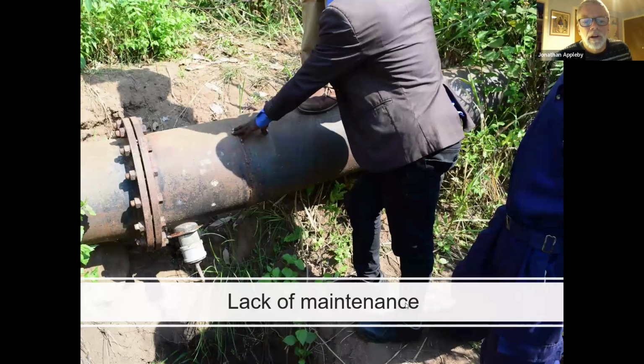One of the main issues over the years was lack of maintenance. Faults, when they occurred, were often left unrepaired or just bodged a little bit. Behind that is the fact that the hospital never had any money for that sort of thing. Money is very tight, and in these mission hospitals there's never enough funds for whatever they want to do. So if somebody comes along saying, 'I need a few thousand pounds to repair this,' it doesn't always get done. The cleaning of the dam hadn't happened very often, so silt had carried down the pipe. Parts had become faulty and had not been replaced in the powerhouse. The isolating valve down in the powerhouse was leaking but couldn't be replaced because of lack of money, and so on and so forth. So that's a major issue.